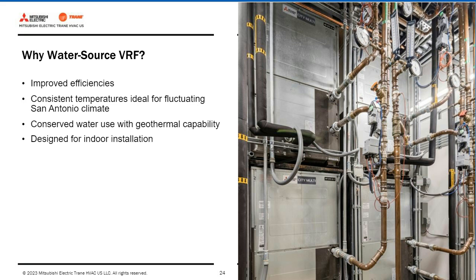By comparison, groundwater temperatures fluctuate a much narrower range, maybe 10 to 20 degrees Fahrenheit. So ultimately, water source systems used in these climates are able to deliver efficiencies 3 to 4 times higher than an air-sourced VRF system. It's important to note that in this area of the country, water is a big deal, if you don't know, because it never rains.